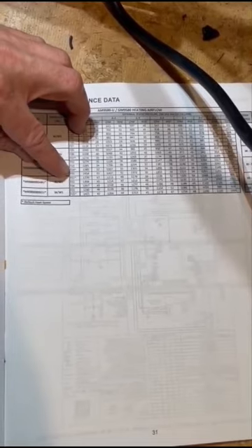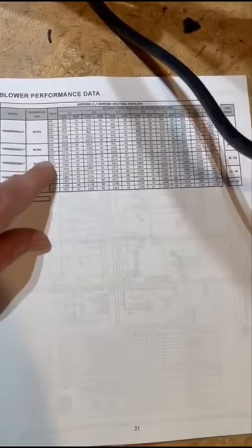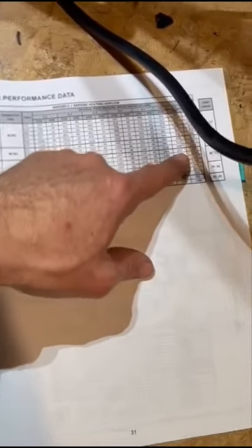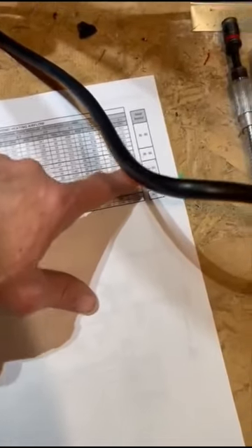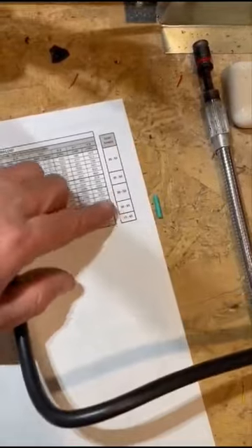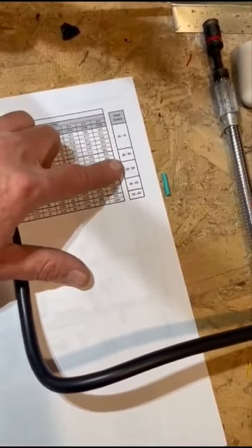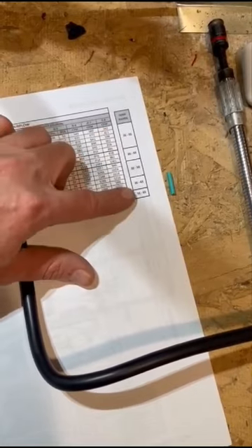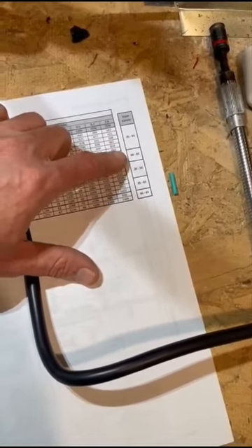Now on the second page, it's the heating chart. So you're gonna go 4-ton 60, factory default is F04. You're gonna go F04, and you're gonna go all the way to the side, and it's gonna show you the airflow, and it's gonna show you the temperature rise. You have the temp rise on different units here. Basically the temperature difference between the supply and the return, what it needs to be so it doesn't overheat.